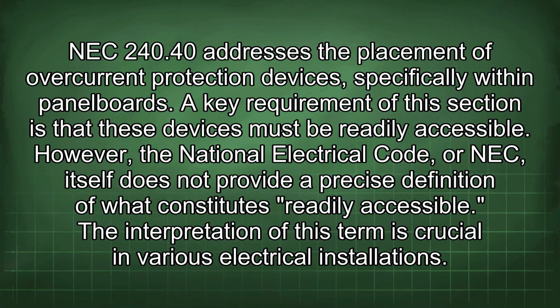NEC 240.40 addresses the placement of overcurrent protection devices, specifically within panel boards. A key requirement of this section is that these devices must be readily accessible. However, the National Electrical Code, or NEC, itself does not provide a precise definition of what constitutes readily accessible. The interpretation of this term is crucial in various electrical installations.